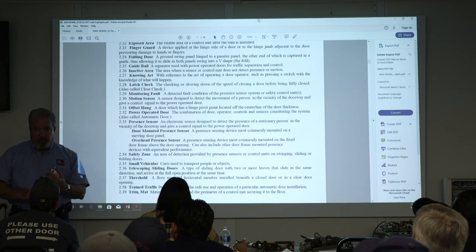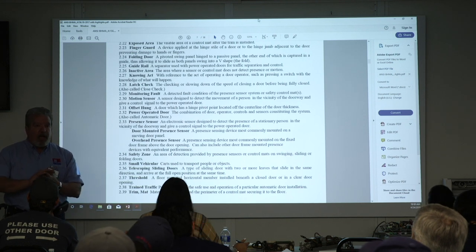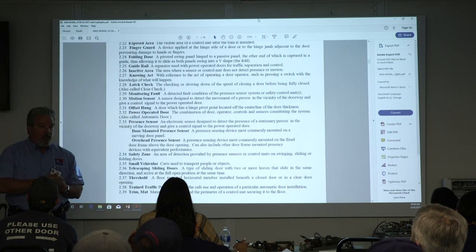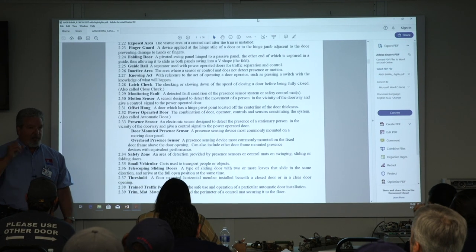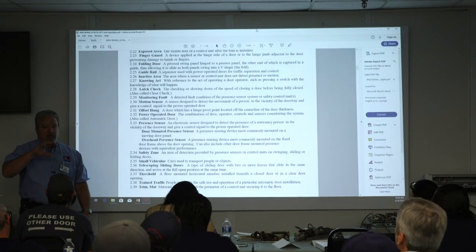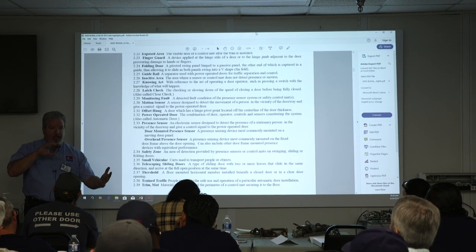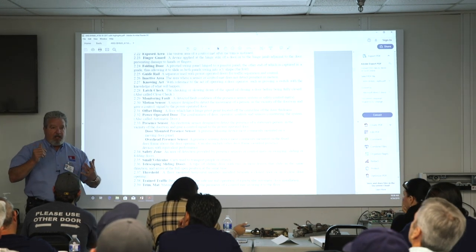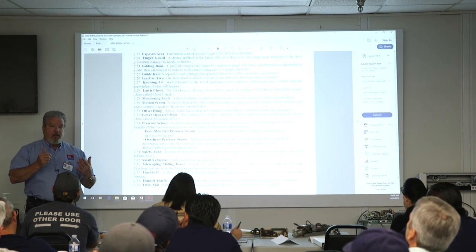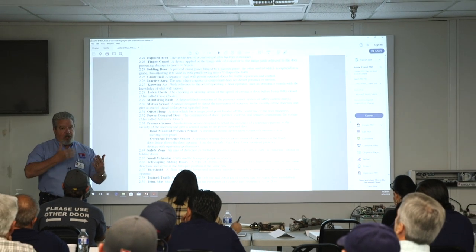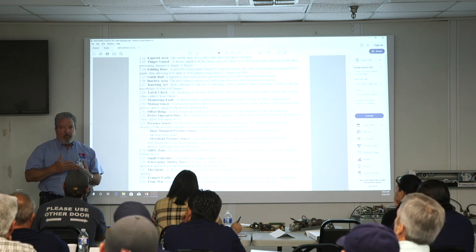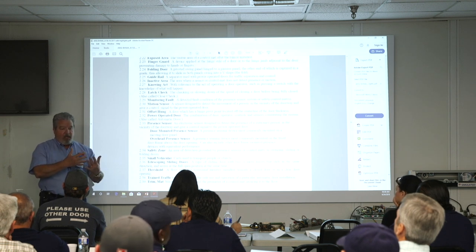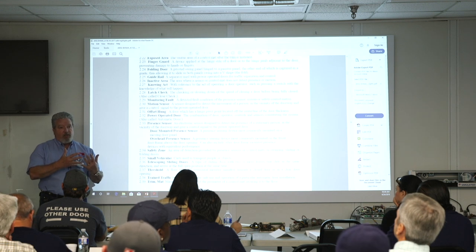And in the world of motion sensors, there's really two primary types of technology being used. We've got microwave, which uses something called the Doppler effect to create a signal, meaning the motion sensor emits these Doppler waves of energy, and it's expecting to get that energy reflected back to it by something moving. When that object is moving, the rate of return of that microwave signal changes, because as you walk toward or away from the motion sensor, the reflectivity of your body on those microwave pulses changes, and that's what creates the signal.